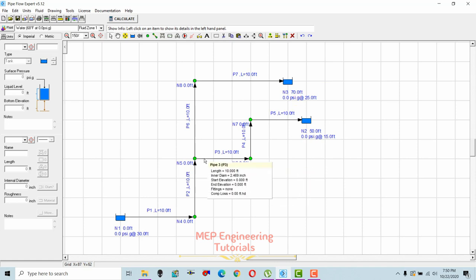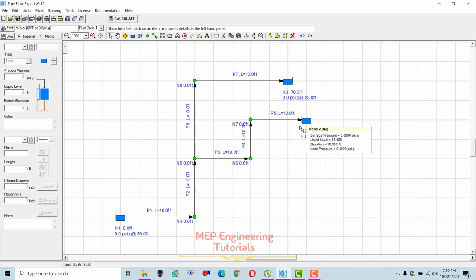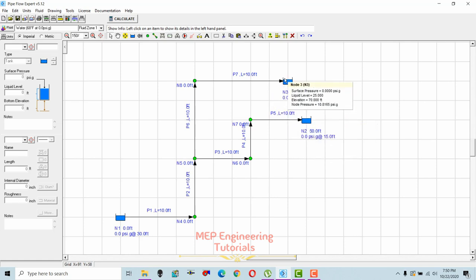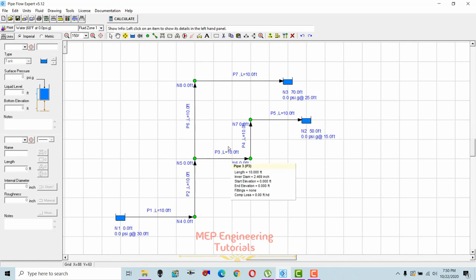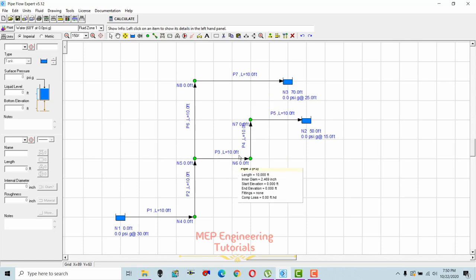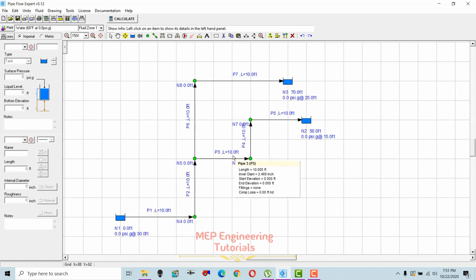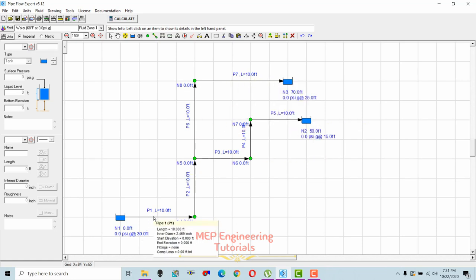We'll assign 80 gpm for Tank 2 and 120 gpm for Tank 3. To control flow — 80 gpm to Tank 2 and 120 gpm to Tank 3 — I'll use one flow control valve on one of the lines, so total flow is 200 gpm, with 80 going one way and 120 the other. First, I'll place the pump for 200 gpm.